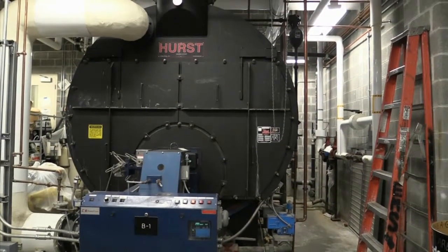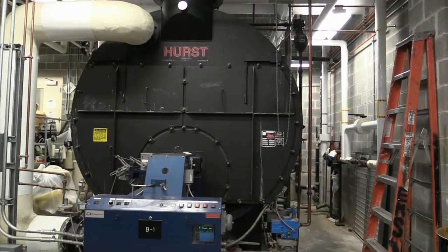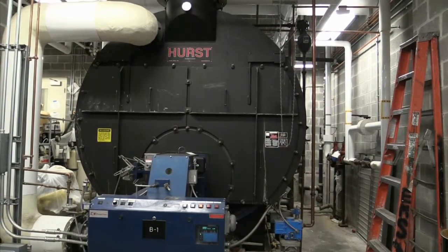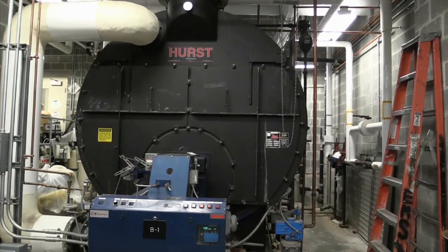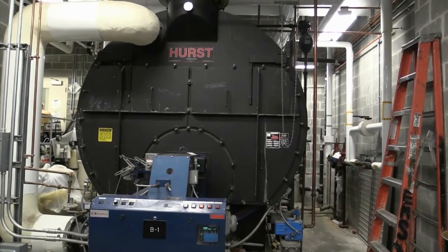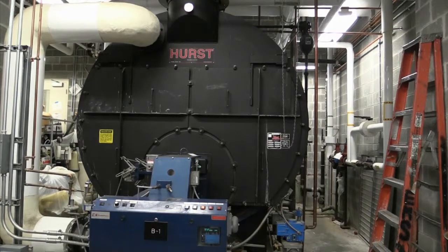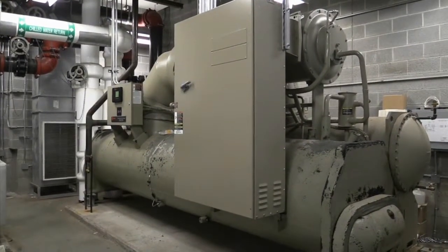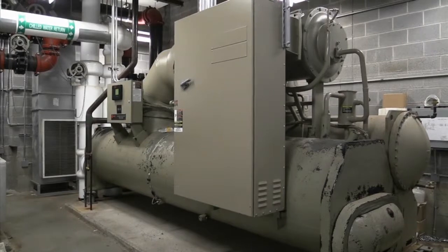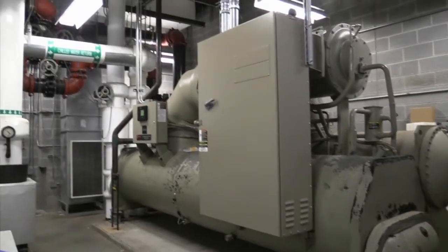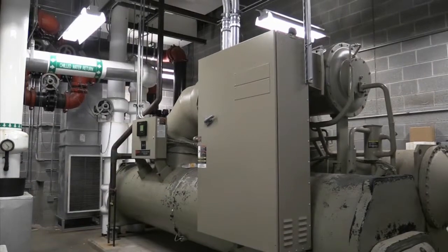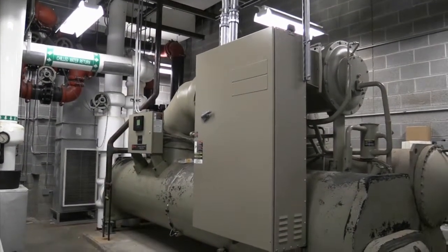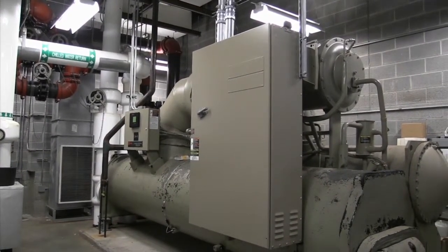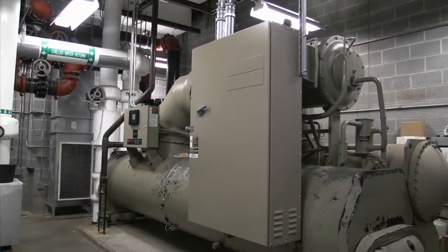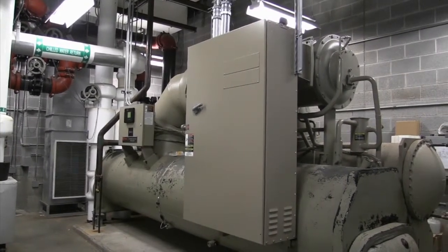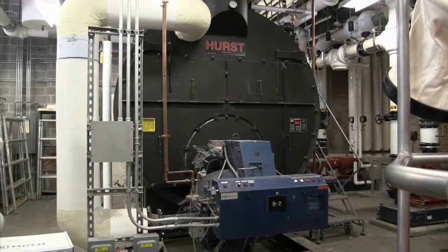While walking down the boiler room, it is determined that the lead boiler is running at temperatures in excess of 170 degrees Fahrenheit, which is typical of cold, winter weather operations. The recommendation is to operate the lead boiler per the vendor's instructions. The vendor does not indicate on their website that their boilers are capable of operating at temperatures below 160 to 170 degrees Fahrenheit. Therefore, it would be prudent to optimize the hot water loop such that the VFD-driven pumps are operating to maintain the minimum differential pressure set points for summer loads.